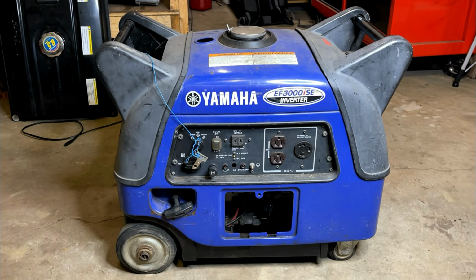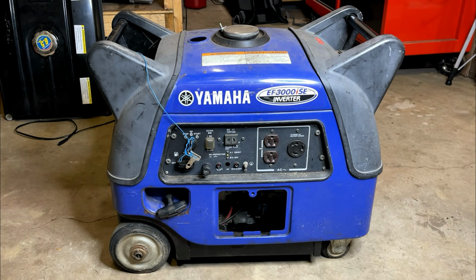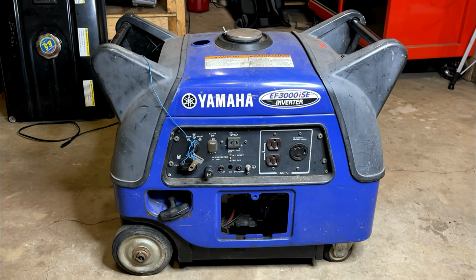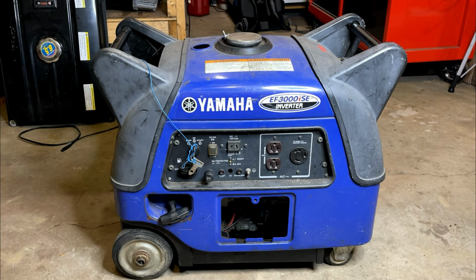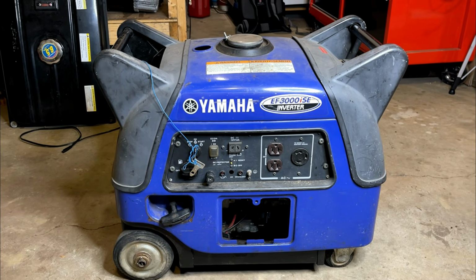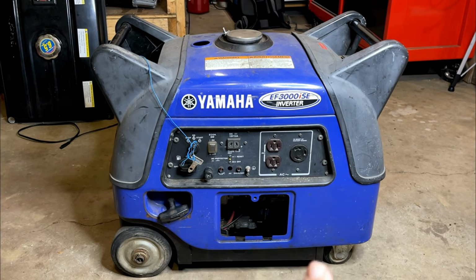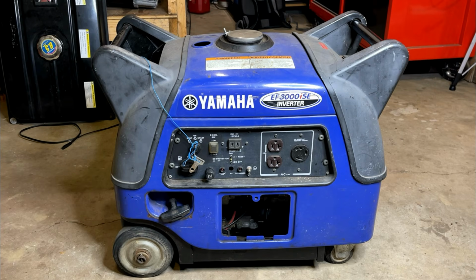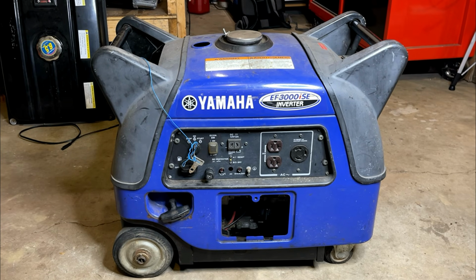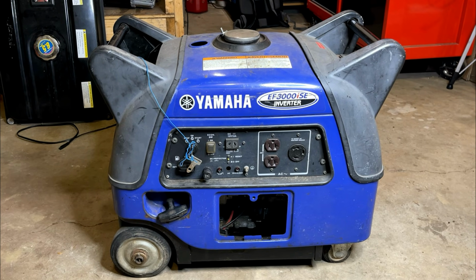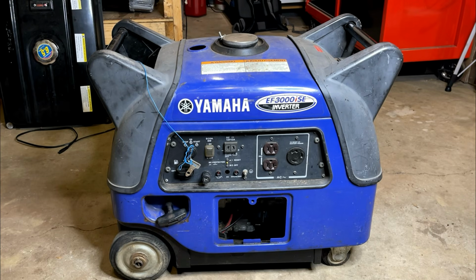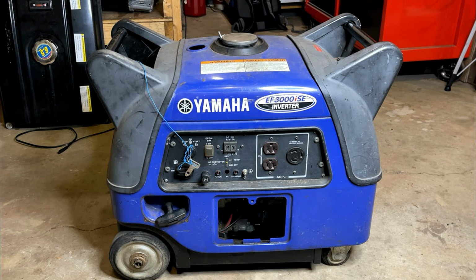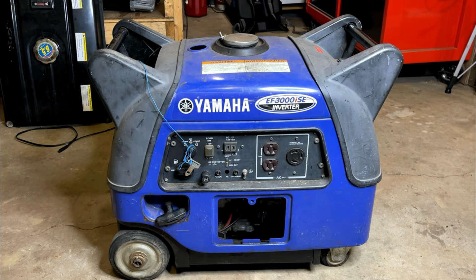Also, there's a mouse nest in there, so we could have some chewed wires, and if the right wires are chewed it could be creating a short circuit. There's no AC breaker on this unit - it's actually up to the inverter itself to detect a short or an overload and shut down to protect itself. So maybe, just maybe, that's what's going on here.